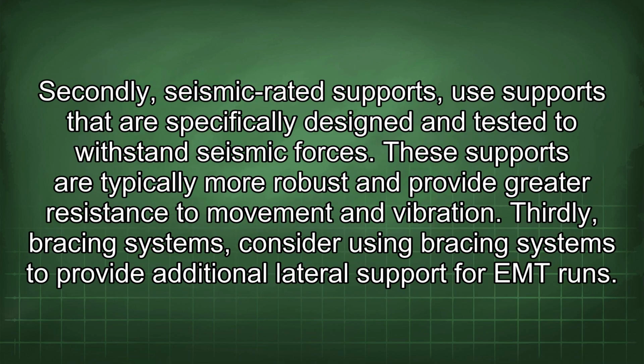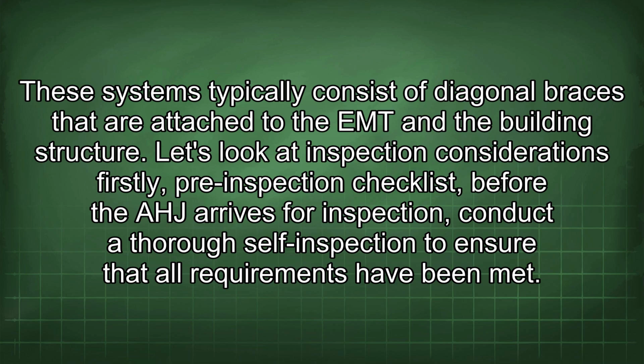Secondly, seismic-rated supports. Use supports that are specifically designed and tested to withstand seismic forces. These supports are typically more robust and provide greater resistance to movement and vibration. Thirdly, bracing systems. Consider using bracing systems to provide additional lateral support for EMT runs. These systems typically consist of diagonal braces that are attached to the EMT and the building structure.